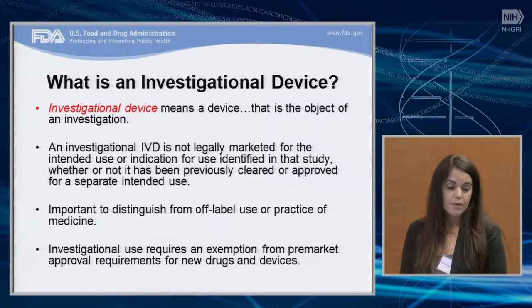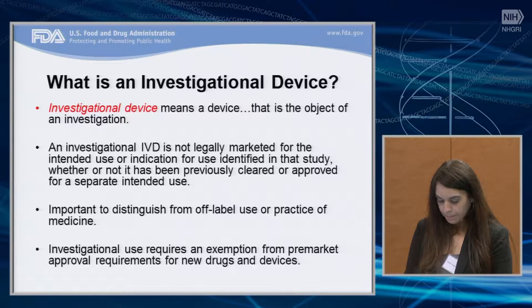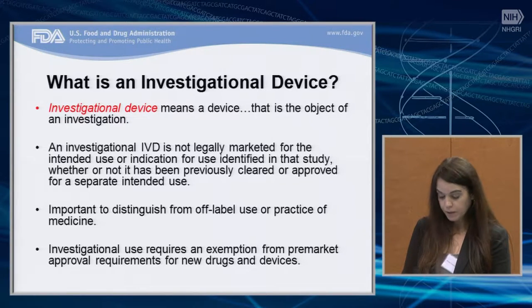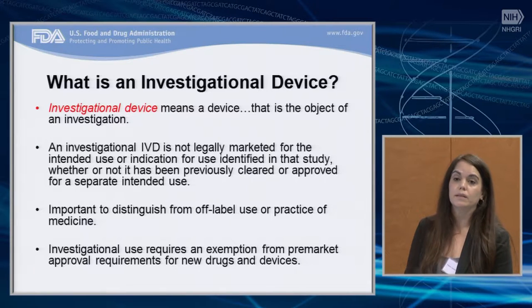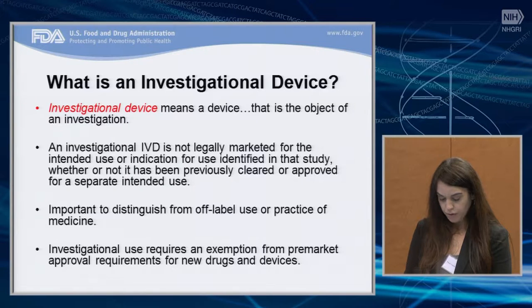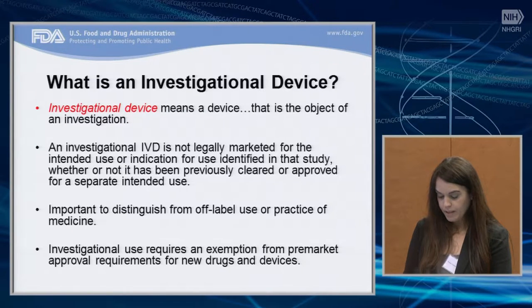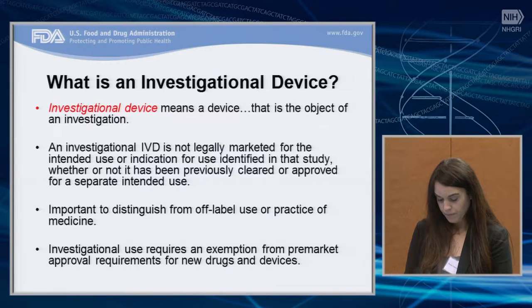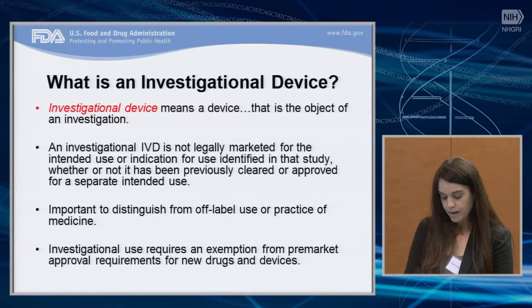Taking all of that together, an investigational device is the device that is the object of an investigation. For example, if the use of the device is included in a clinical protocol, then the device may be investigational. If the device is not legally marketed for the intended use or indications for use identified in the clinical protocol — whether or not it's been previously cleared or approved for a separate intended use — then the device is investigational. We distinguish investigational use from off-label use or practice of medicine. Investigational use requires an exemption from pre-market approval requirements for new drugs and devices.